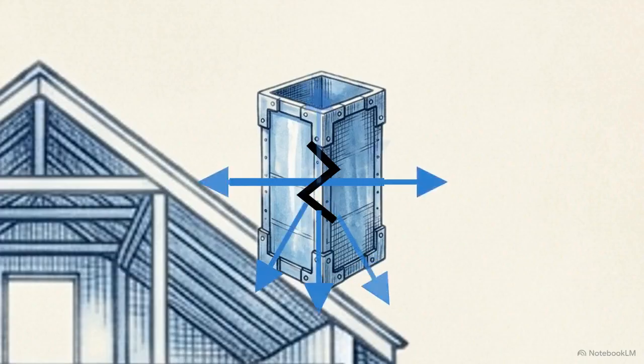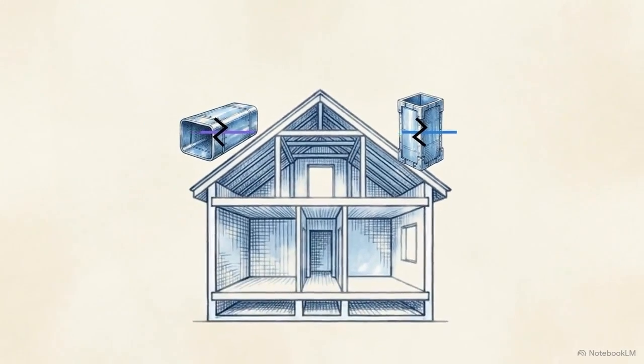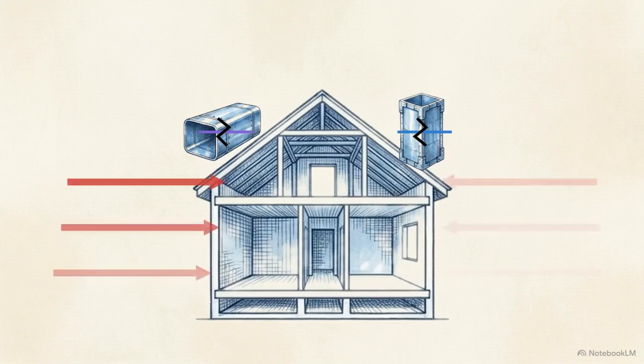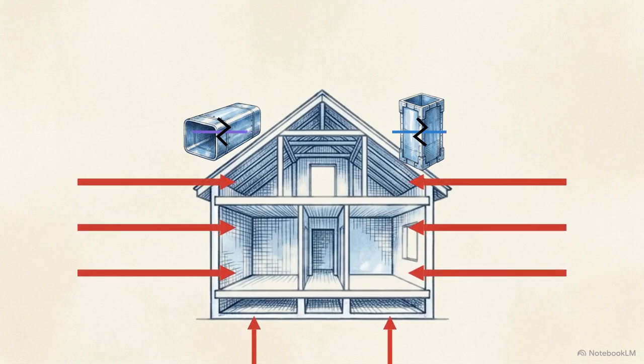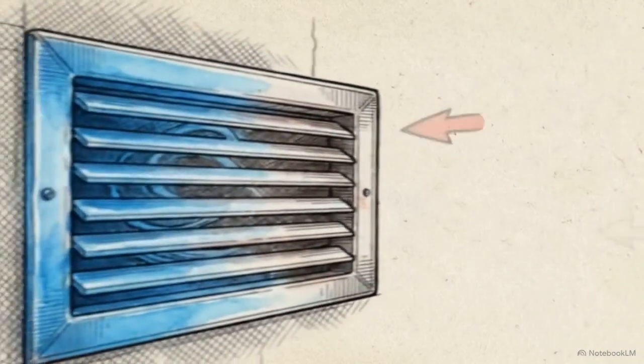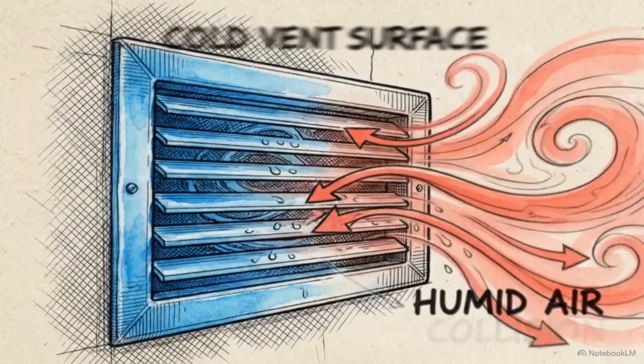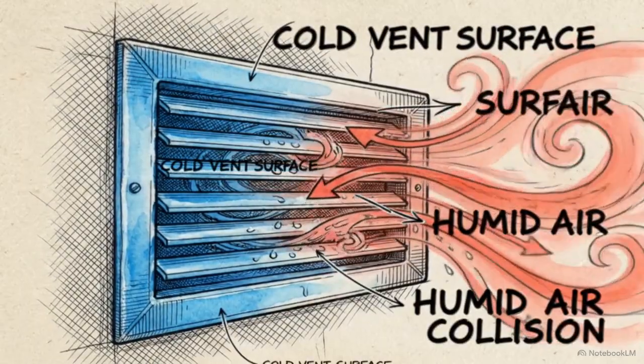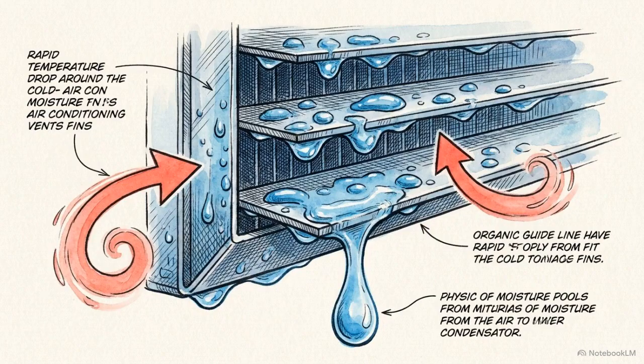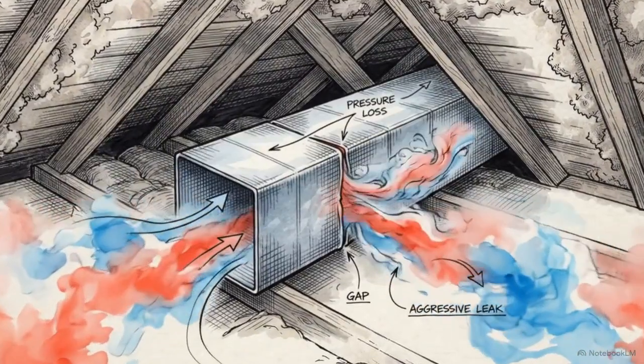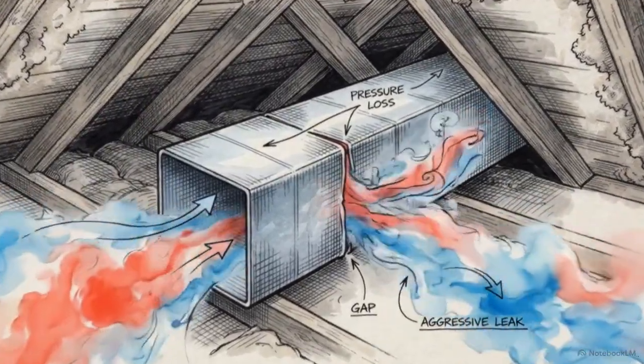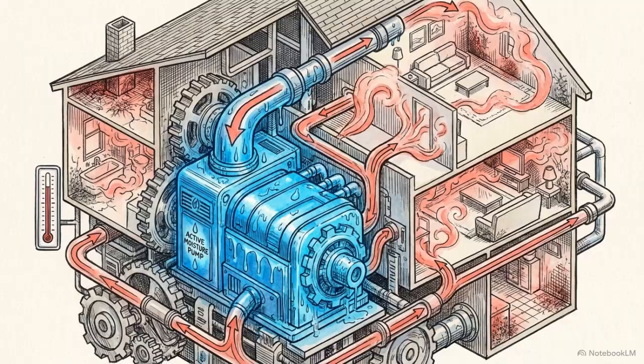The physics work in reverse on the other side. A leak in the supply duct blows conditioned air into the attic. Because the home is losing air volume, the house is forced to pull in hot replacement air from the outside, through utility chases and window gaps, to equalize the pressure. Once that humid outdoor air breaches the walls, it collides with the cold surfaces of the interior drywall and the metal air conditioning vents. The sudden temperature drop forces the moisture in the air to condense into liquid water beads. A mechanical failure as small as a quarter-inch gap in an attic duct forces the interior climate to mirror the humid outdoors. The HVAC system now acts as an active moisture delivery engine.